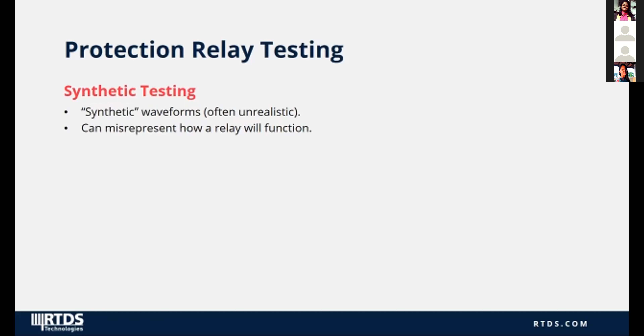For example, a signal generator will generate waveforms that model, let's say, a lightning shock. These theoretical models and waveforms may not represent actual values. As a result, it can misrepresent how a relay will function in service. The second approach is playback testing, where recorded or simulated waveforms are sent to the relay. This is an open loop testing approach and the most widely used form for relay testing.